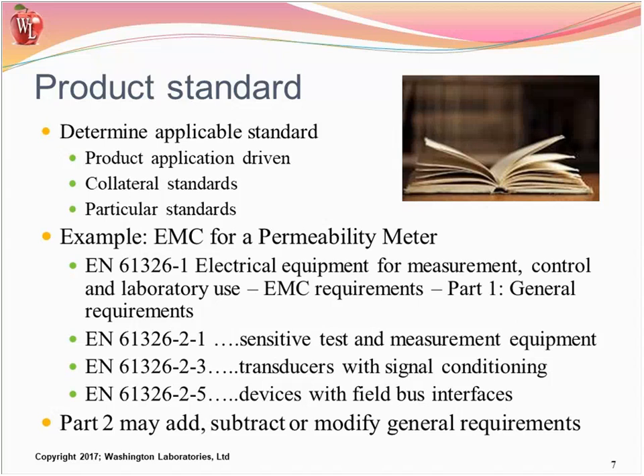A lot of product standards today are hazard-based, and they're becoming more so. You need to take care of a risk analysis or risk management process to identify the risks, and this could incorporate bringing in requirements not currently in the product standard. For instance, a new technology that hasn't been caught in the update yet may be being evaluated, and the risk management system analysis identifies a specific risk that requires evaluation. That's part of your risk management standard, and you need to have that as part of your file, showing what you've accomplished and what you've done to reduce the risk to an acceptable level, or to a no-risk situation, depending on the particular item.